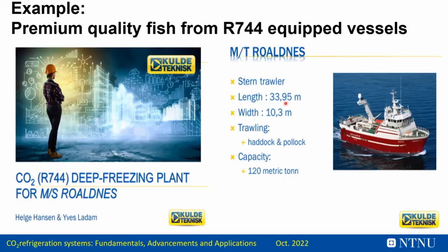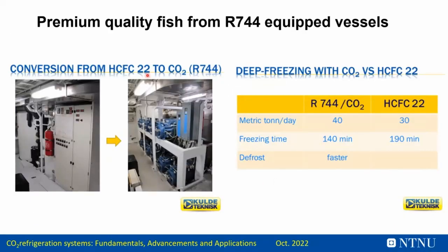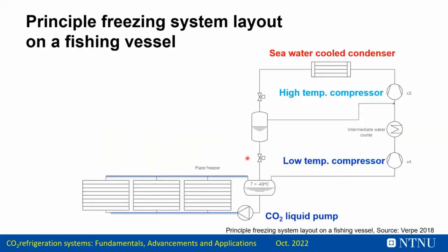It's a small stern trawler. The capacity is normally 120 metric tons a day, and they previously had an R22 system on this ship, which you see on the left hand side, and at the same place inside the ship they implemented the CO2 system. They could increase the number of metric tons per day. Sorry, it was 30 before, and now it's 40. The freezing time was significantly lower, and the defrost was very fast when they used this equipment with the plate freezers. This is typically how the system looks.